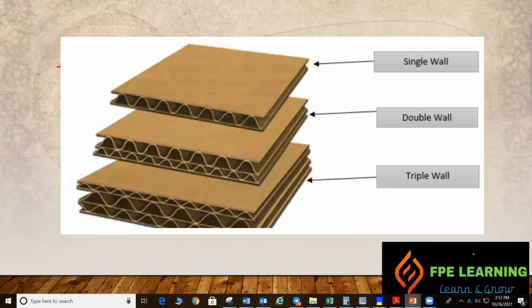So if you look at these cartons, they mostly come as single layer cartons or multi-layer cartons. We assume multi-layer cartons, and we assume a class 2 product because non-combustible product is packaged inside the cartons. So up to this point it is a class 2 product.